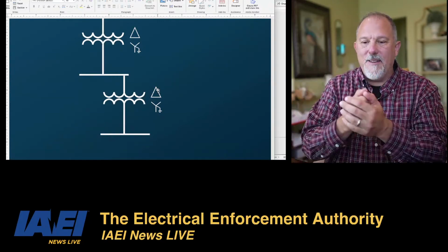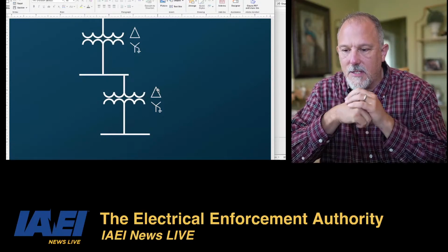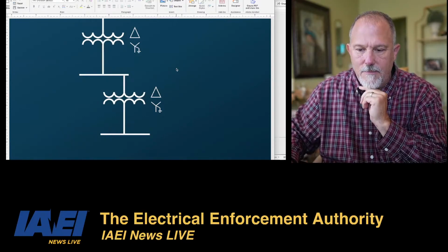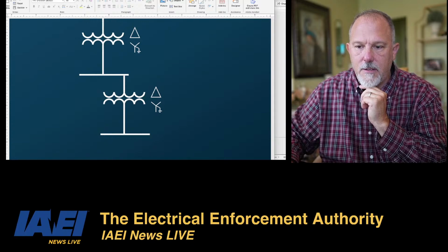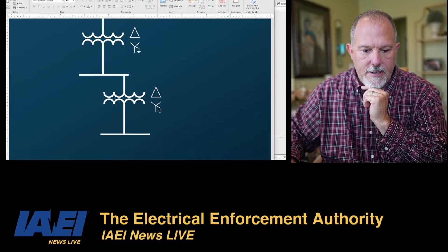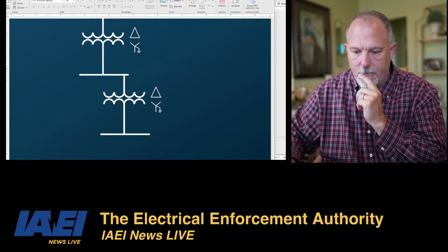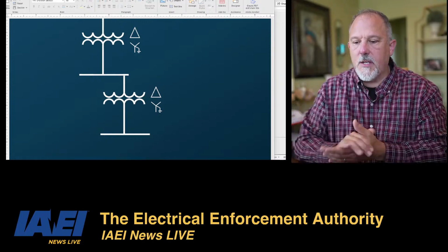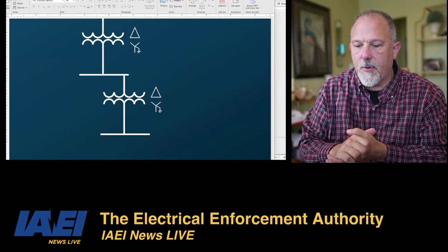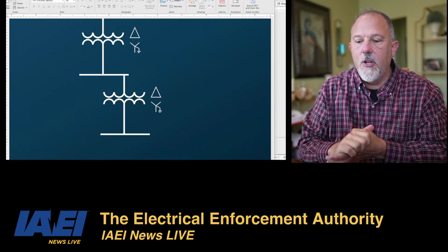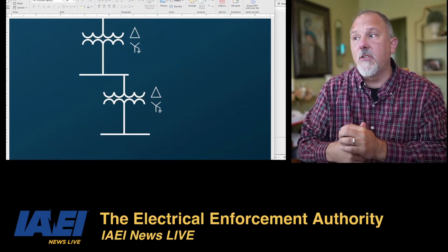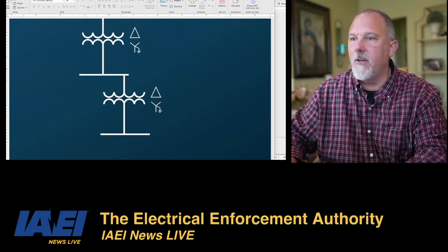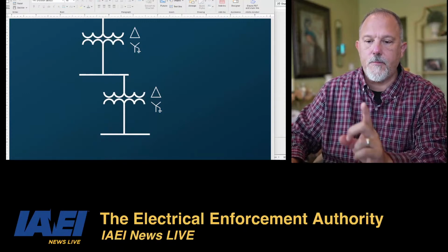Yeah, thanks for pointing it out. The reason I asked is because since it's not a service, I assume it's on the premises. I was assuming the delta would be grounded as well, unlike a service. So again, the delta on the transformer is not grounded.